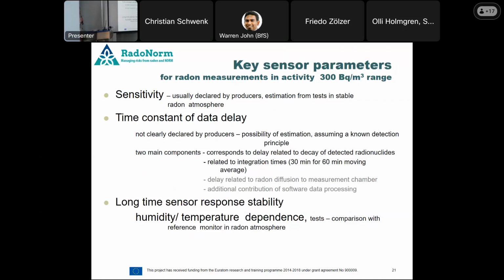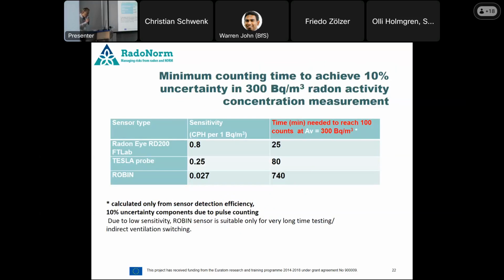Considering that a sensor to be applied for direct ventilation control should be able to correctly and quickly measure 300 becquerels per cubic meter, the key parameters are their sensitivity, delay constant, and stability. Sensitivity is usually declared by the producer, but usually only at one activity point. The table illustrates how important overall sensitivity is for the counting time to achieve 10% uncertainty at 300 becquerels activity. It shows differences between the tested sensors, with Robin needing about 12 hours to count 100 pulses at 300 becquerels per cubic meter activity level.